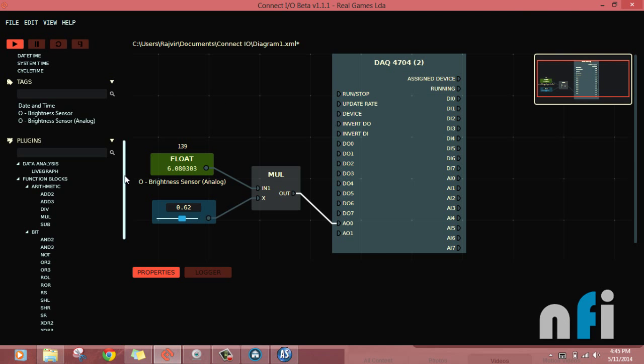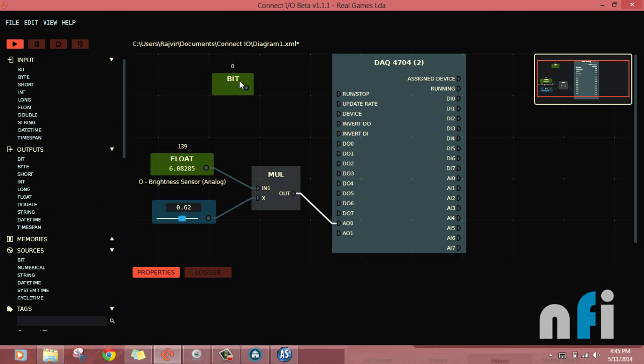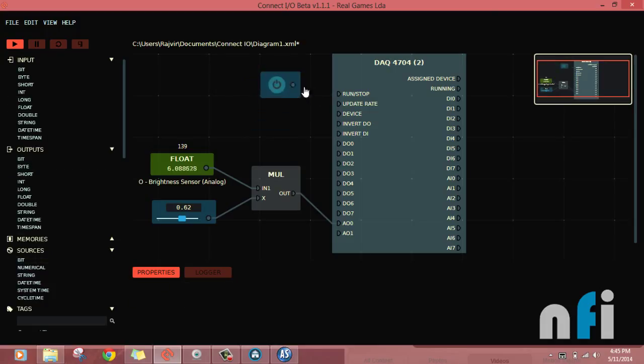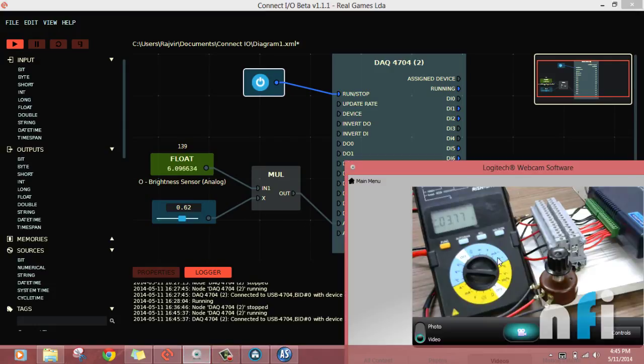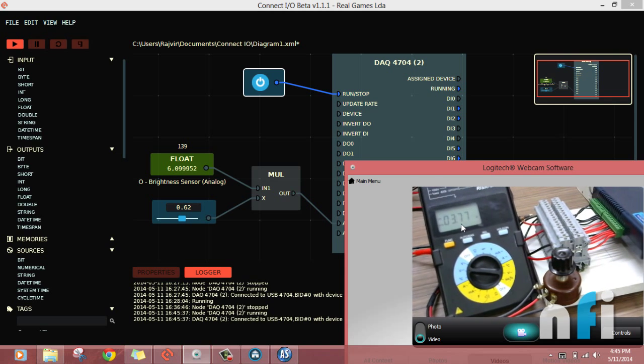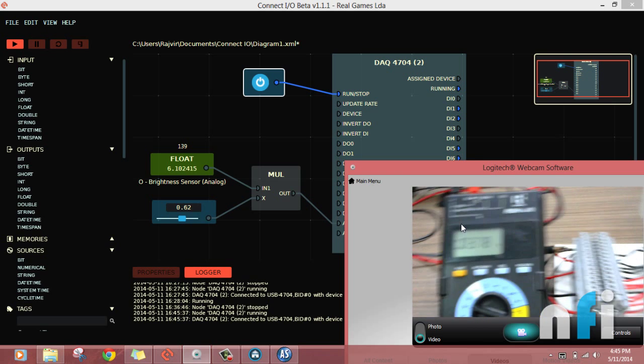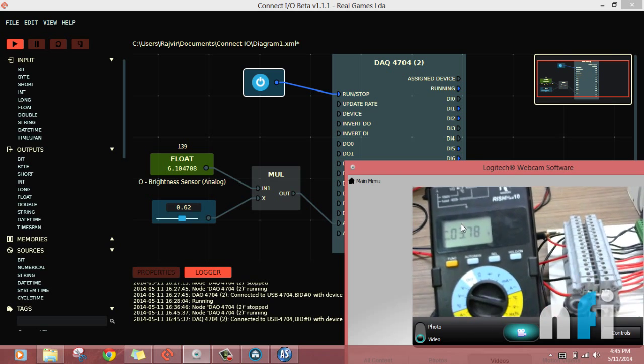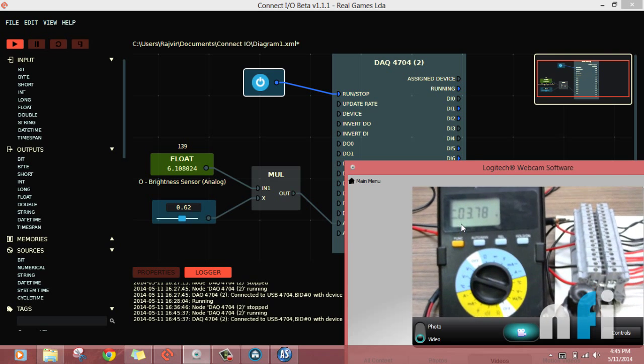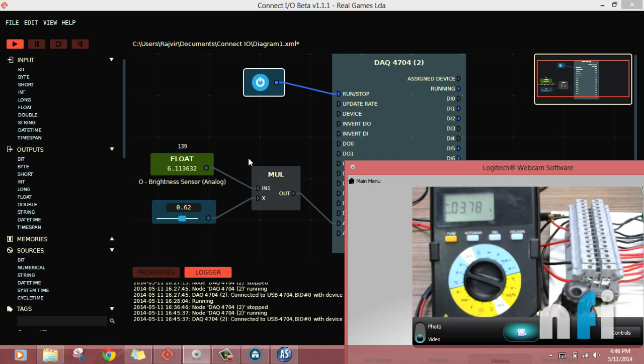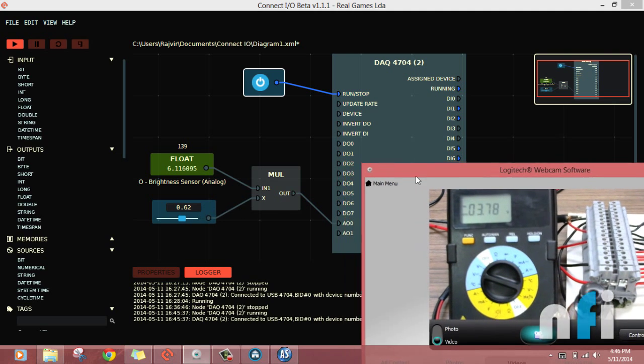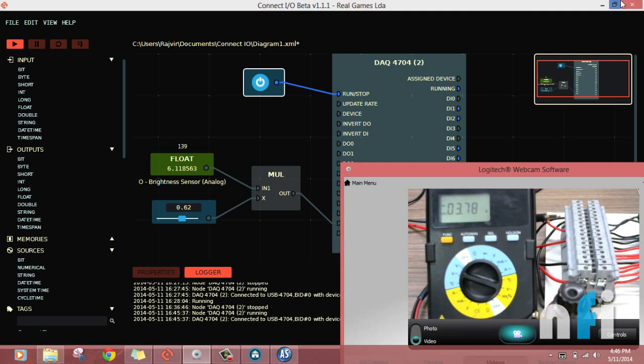Now let's go to Connect IO. I need a source bit to run the DAQ card. When I run the DAQ card the multiplication is applied and we have a voltage of 3.7 volts on the multimeter. This voltage corresponds to the luminance reading from the daylight sensor, which converts luminance into bits that we scale to the zero to five volt range.